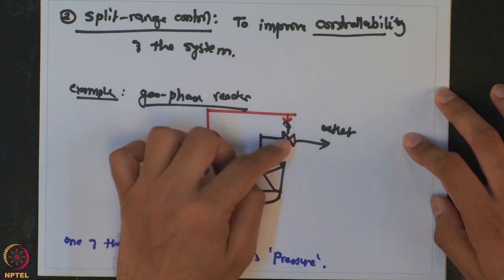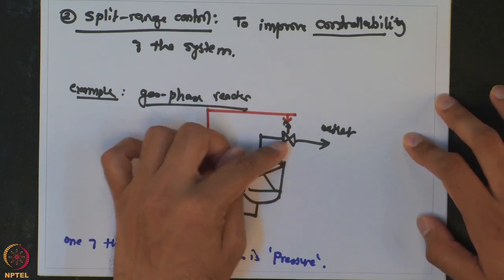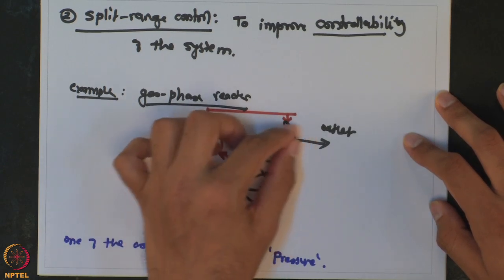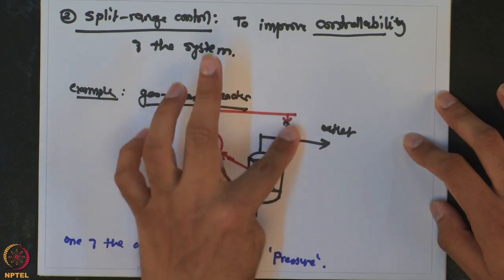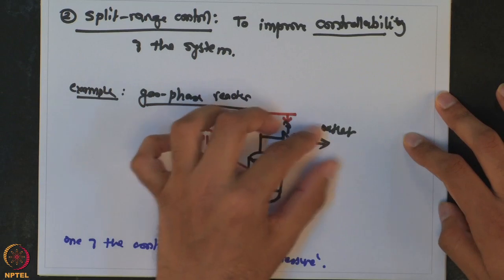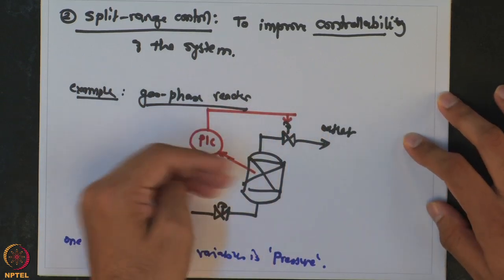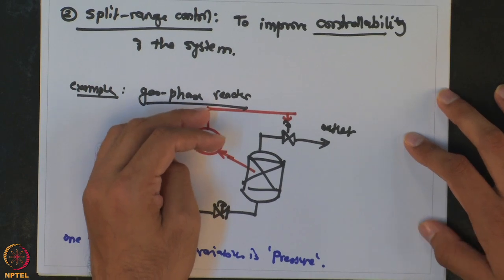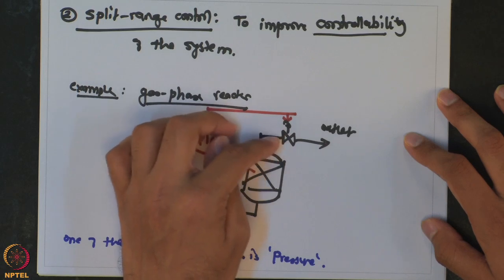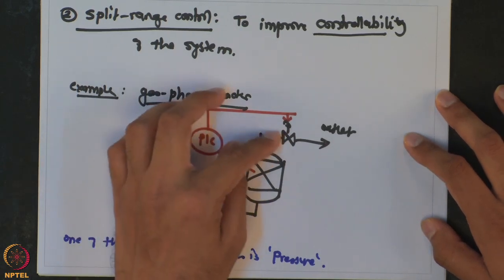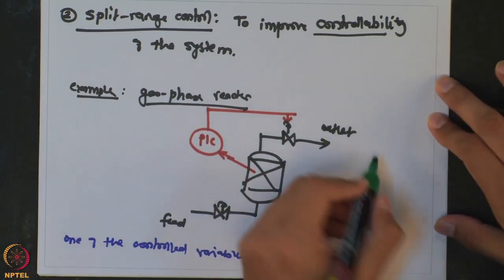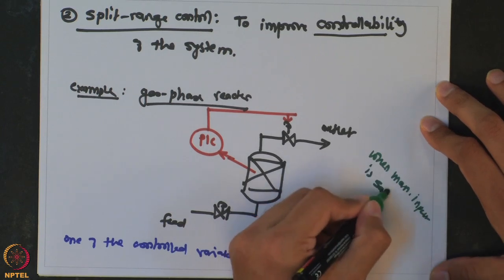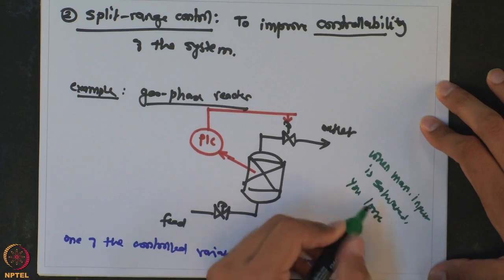When the valve is completely open, it is as good as having no valve — the entire pipeline carries vapor out. But in a runaway situation where a lot of vapor is being generated, it may not be sufficient to maintain pressure; pressure will keep building because there is no way to manipulate it anymore. You have lost controllability because the manipulated input is saturated. When the manipulated input is saturated, you lose controllability.